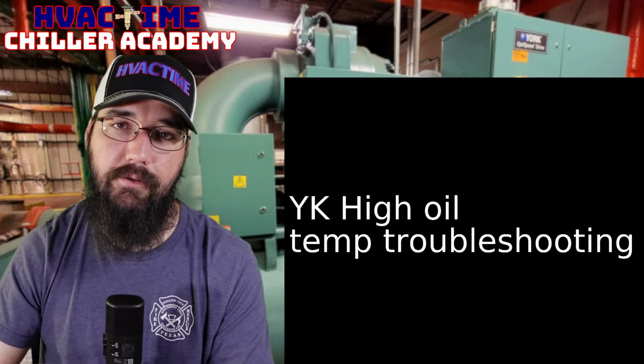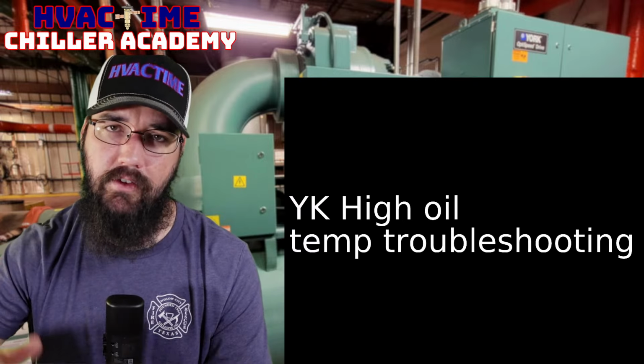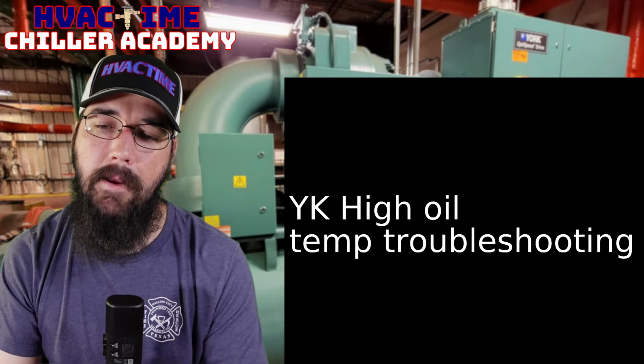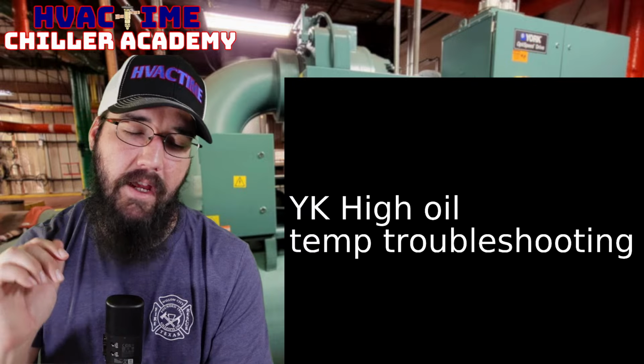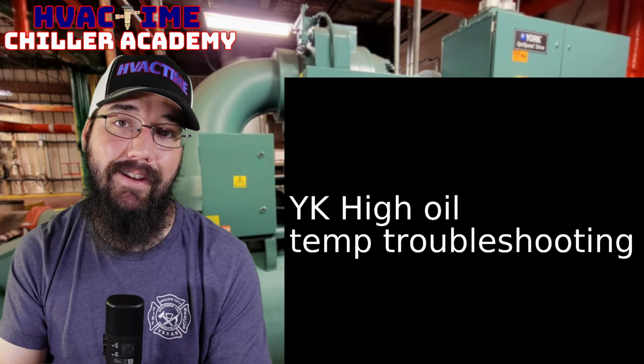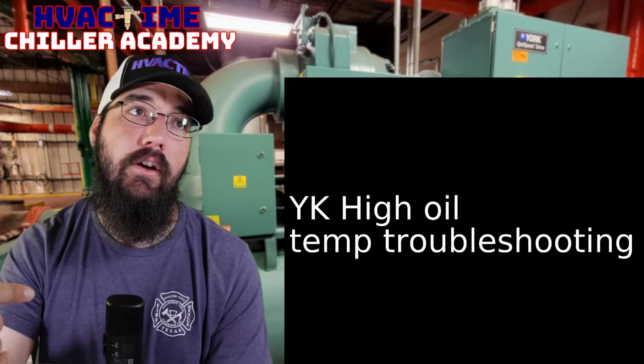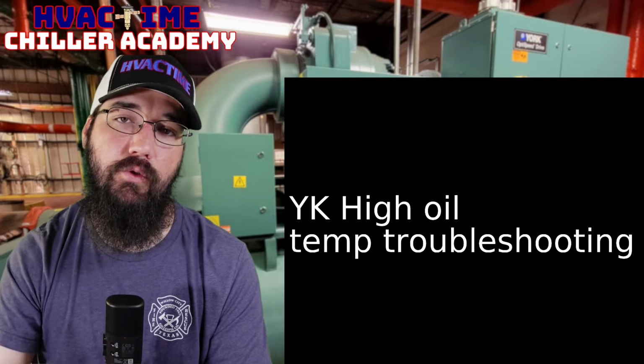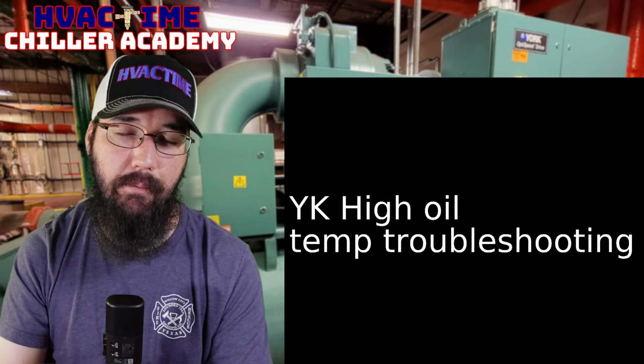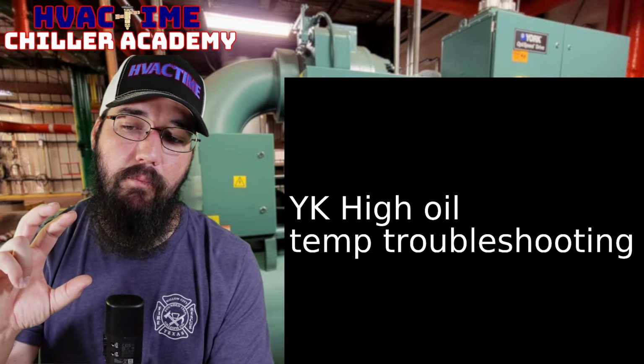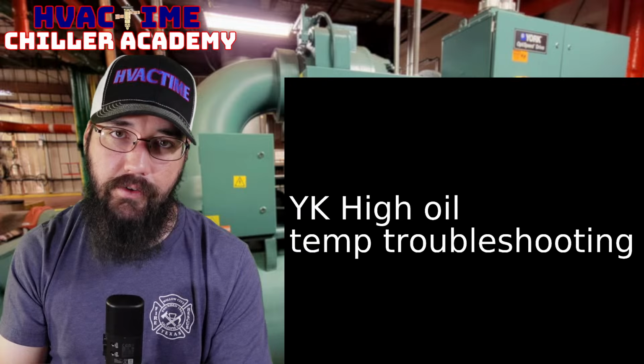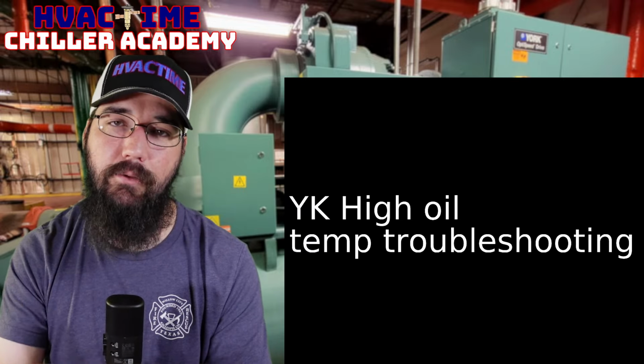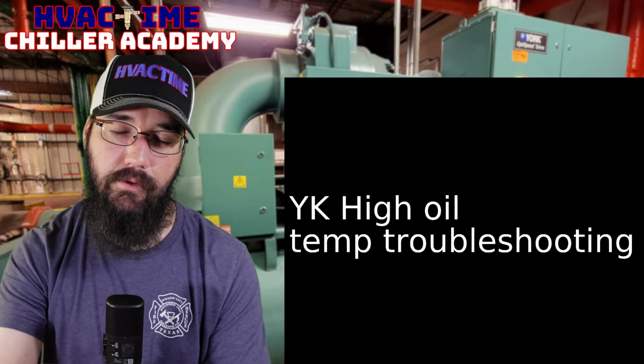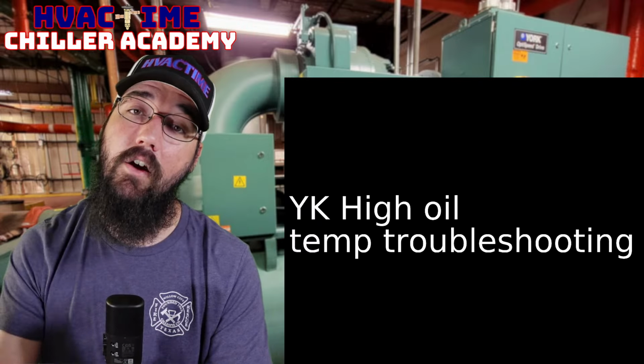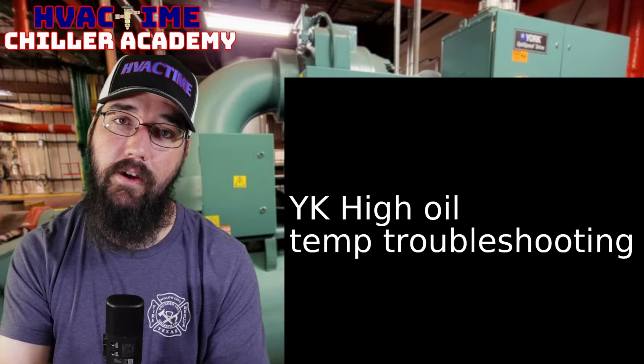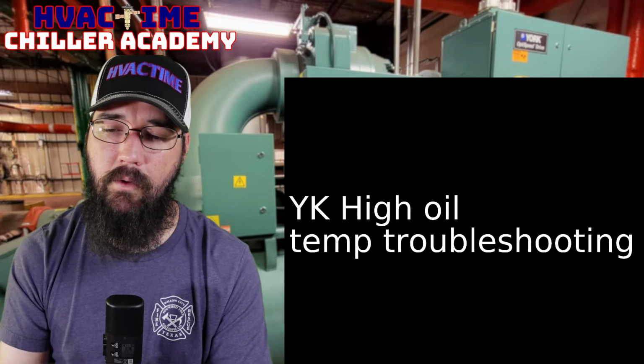This goes back to some of our saturation talk earlier as to why that subcooling would go up or down. It's a separate conversation, but that's going to come back to your load. So if you're only seeing 4 or 6 degrees at load, when you've truly got this machine loaded and you're running close to design TD, temperature difference across the evaporator, and everything is really stacked up, and you're only seeing 4 or 6, I have questions. Why are we still that low? Those are derated part load numbers, not loaded numbers. We need to resolve that, which plays back into whether we are feeding enough to that metering valve for the oil cooler. All of that plays into the same conversation.